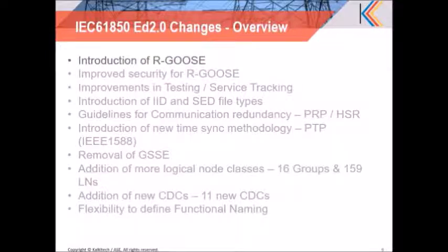Now in Edition 2, as well as 61850 90-5 for PMU data exchange, the R-GOOSE concept was introduced. And this routable GOOSE model is targeted at the GOOSE mapping onto the UDP layer. So this can be extended further beyond the router levels onto other substations and other scenarios.